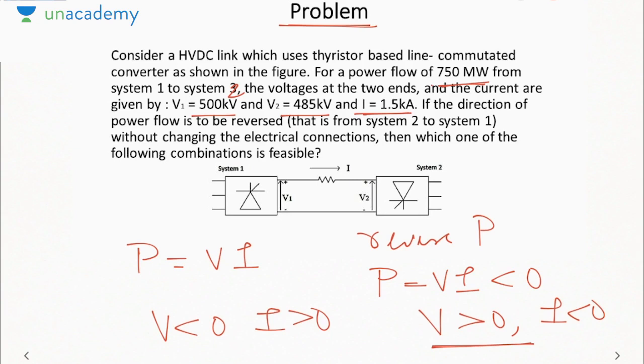One thing also to remember in HVDC is that current will always flow from higher voltage to lower voltage. That is, if I is flowing in this direction, then V1 must be greater than V2. So current direction depends on the magnitude of voltage, and to reverse the power flow, either reverse the voltage polarity or reverse the current direction, but not both. Because if both become negative, then their product would still be positive. So the direction of power flow would still be the same.